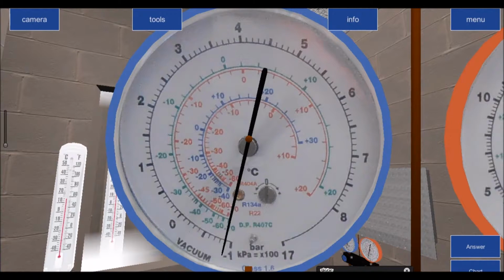And the one thing that you will notice, even though these temperature ranges are different for equal pressures, is that the higher we go up in pressure, so we're up at 8 bar here, you can see 407C is plus 20. You can see this red one, which is R22, is at plus 20 up around 8 bar, or just above 8 or 7.5 bar there, maybe even less. You've got plus 10 degrees for 404A just over 6 bar, so going across there, 6.1, 6.2. You've got plus 30 degrees for 134A. I think this is the blue one here, 134A.